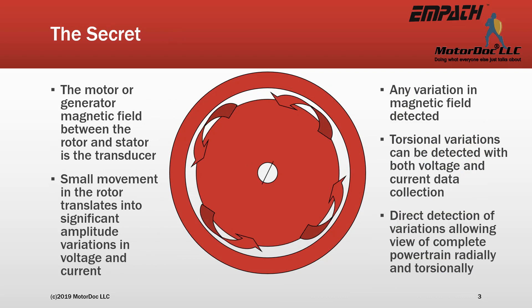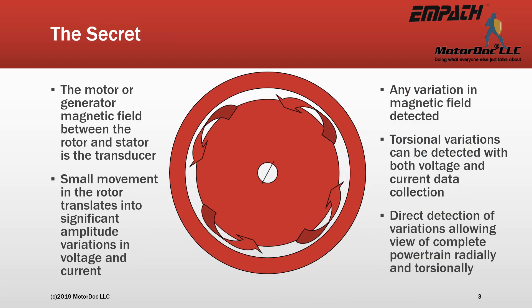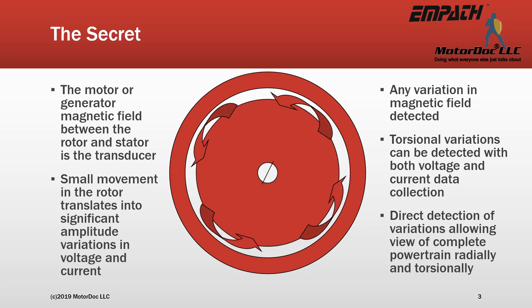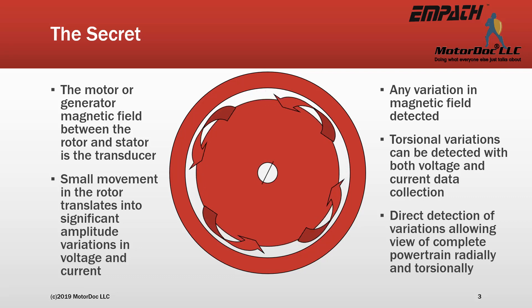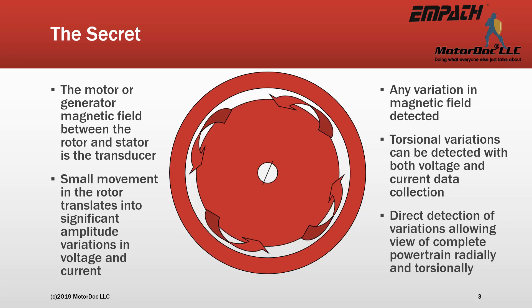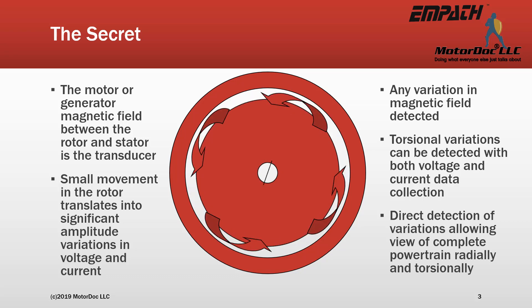In a perfect motor, the rotor is centered in the stator and all fields are even. If a perfect voltage sine wave is introduced, a perfect current wave results. If there are any defect frequencies in the voltage sine wave, those frequencies will appear in the current FFT but at a smaller magnitude due to the dampening effect through the motor and fields. In order to compare equivalent magnitudes, the results of both are shown in dB.